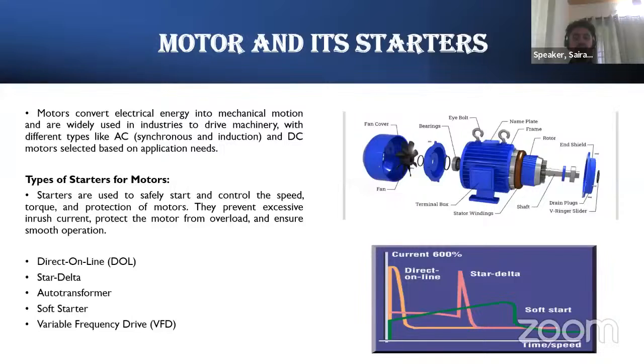The direct online starters are there. Then star delta, auto transformer, soft starters, variable frequency drives are there. If you look at the graphs shown here, soft starters are more convenient for starting the motor. Rather than starters, variable frequency drives can be used at the point where there will be various fluctuations of loading for the operation. There, variable frequency drives are the better option. Additionally, they will be playing the role of starter also. Also, they will help us in terms of energy efficiency practice, where there is a huge amount of load variation in the application.